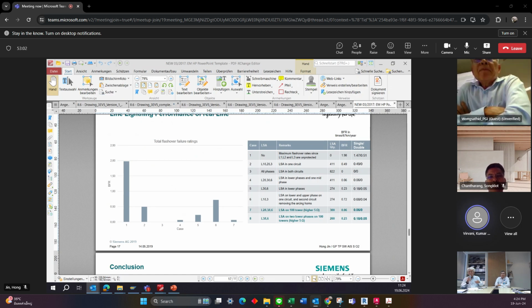And yeah, definitely, as Hong mentioned, if we install our EGLA in parallel to the insulator, we don't need to worry about reducing the tower footing resistance, because when we install our EGLA, it will take care of the back flashover phenomenon, which generally occurs during lightning activity. I can say the most probable cause of a lightning flashover across an insulator is back flashover only. But if we protect our insulator with a lightning arrester, there will not be any back flashover in the system, so we don't need to worry about reducing tower footing resistance.